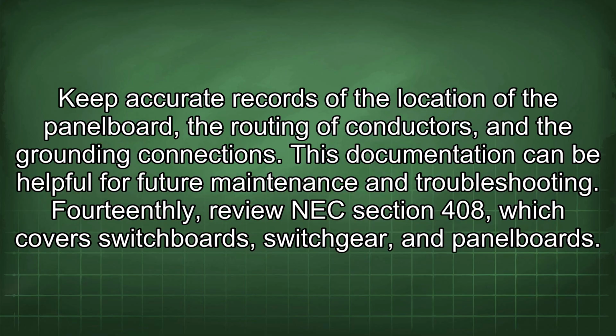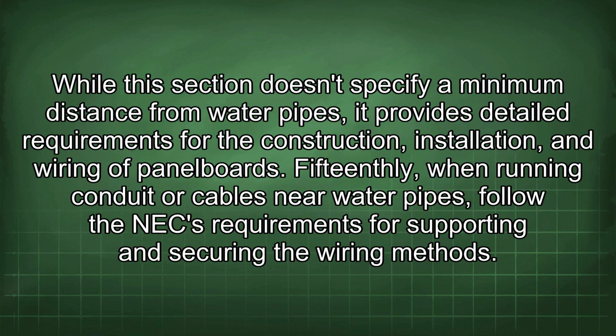14thly, review NEC Section 408, which covers switchboards, switchgear, and panel boards. While this section doesn't specify a minimum distance from water pipes, it provides detailed requirements for the construction, installation, and wiring of panel boards. 15thly, when running conduit or cables near water pipes, follow the NEC requirements for supporting and securing the wiring methods.